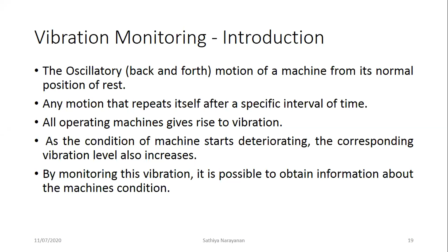So if you think of vibration, all the rotating equipment in the oil and gas industry, such as pumps or compressors or turbines, they all produce some minor vibration. Now, what happens is when the machine starts deteriorating over a period of time. When the machine is new, the vibration will be very, very less. But over a period of time, when the machine gets old, the vibration gets increased. So by monitoring this vibration, we can obtain information on how the machine condition is. Let me say the vibration has increased over time. We can say that the machine may fault in the next 2 years or something like that, so it is time to replace that particular equipment.